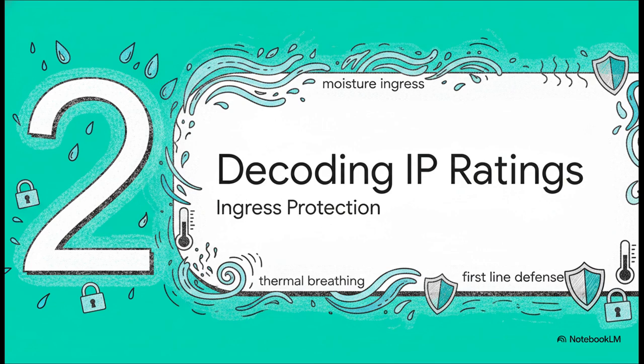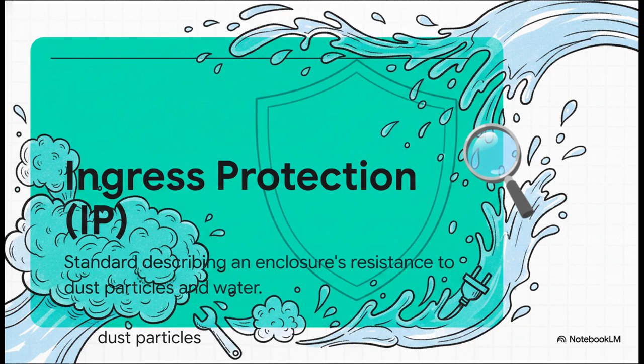Well, let's get into our first line of defense with Section 2, decoding IP rating standards. So, IP. It stands for Ingress Protection. It's a very specific, standardized method set by the International Electrotechnical Commission under the standard IEC 60529. In plain English, it tells us exactly how well an electrical enclosure can withstand dust particles, solid objects basically, and water. It's a totally crucial metric. Without it, we'd just be guessing, calling things splash-proof, which, let's be honest, is a fast track to broken equipment or worse, someone getting hurt.